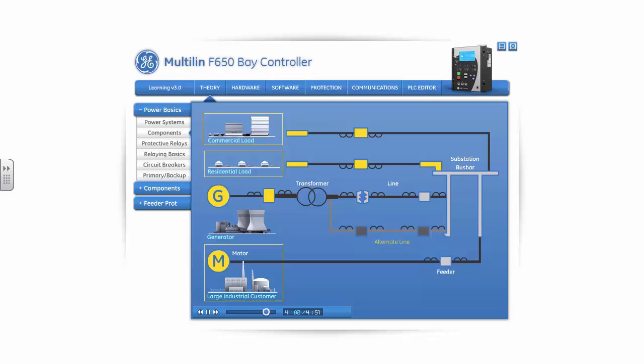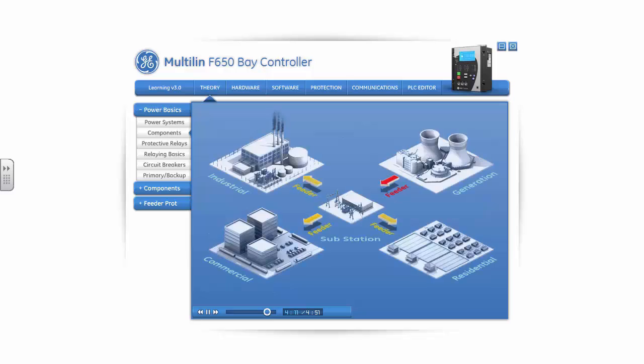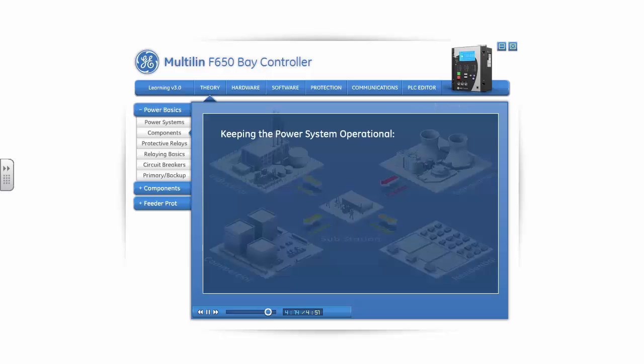To ensure both maximum return on the investment and to provide reliable service to satisfy customers, the whole power system should be kept in operation. This is accomplished in two ways. The first is by the specification of the design and the maintenance of each component of the power system to prevent a failure which would affect the component's usefulness in the power system. The economic considerations of design and maintenance procedures will allow this to proceed only so far.